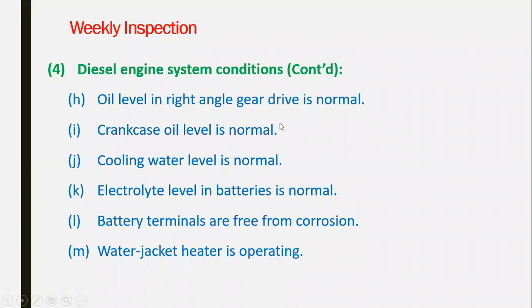Crankcase oil is normal. Cooling water is normal. The level of the cooling water, if with this one, it's applicable for the big motors, if it has a cooling system, a cooling water system. The electrolyte level for the batteries is normal. The battery terminals are free from corrosion. Water jacket heater is operating.